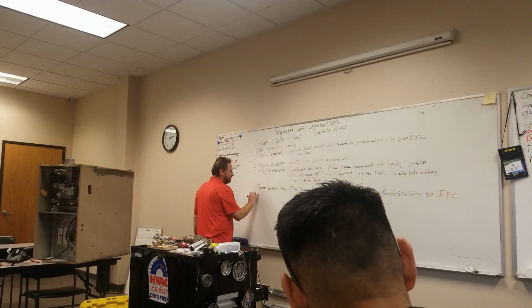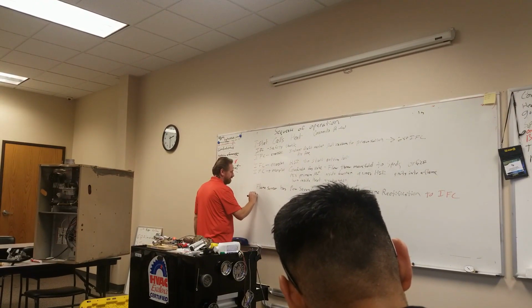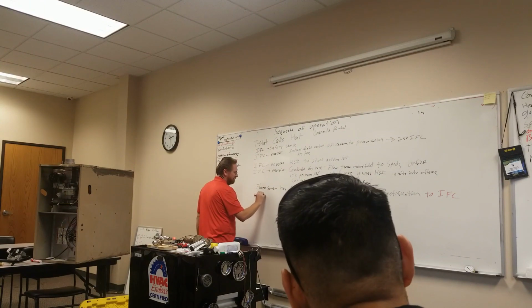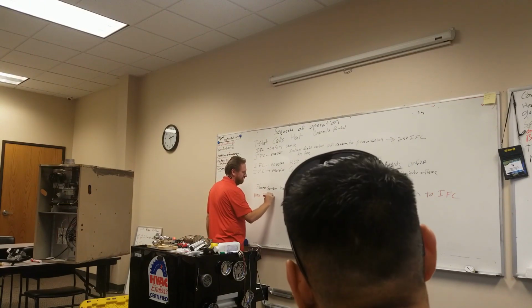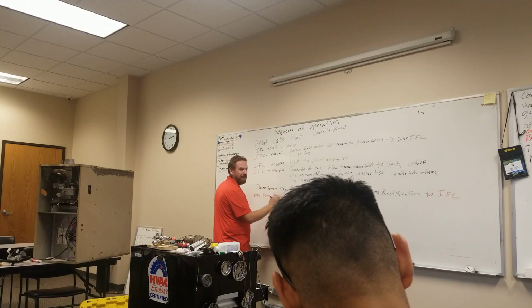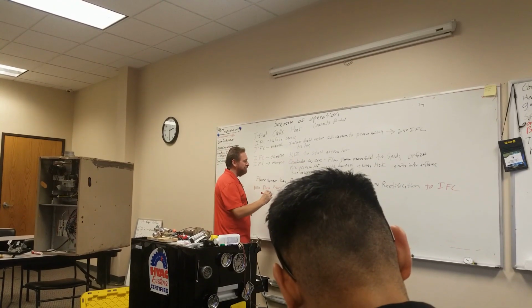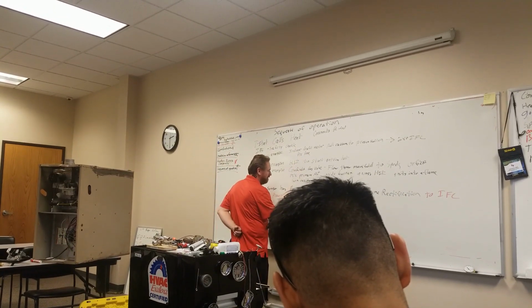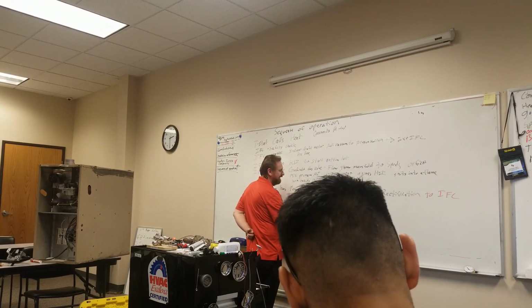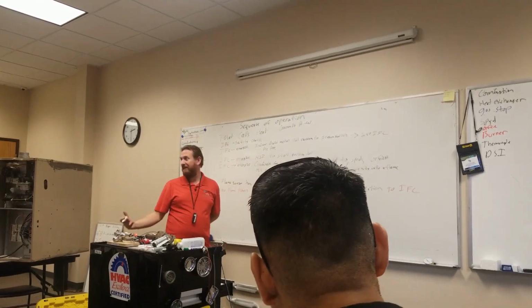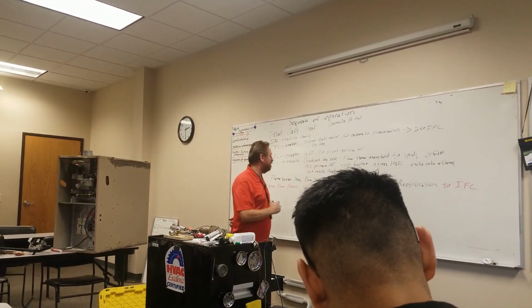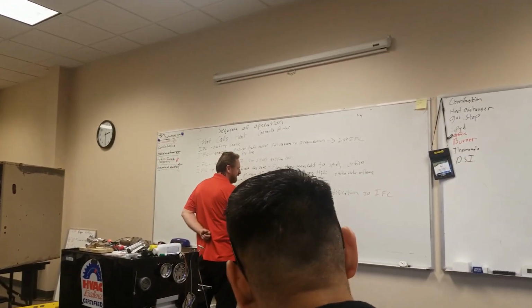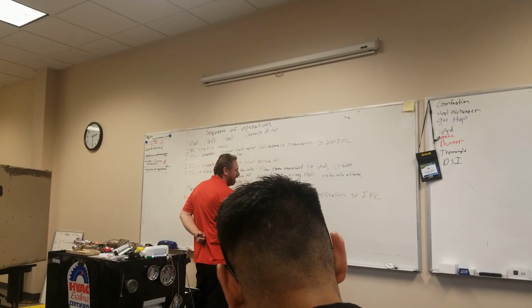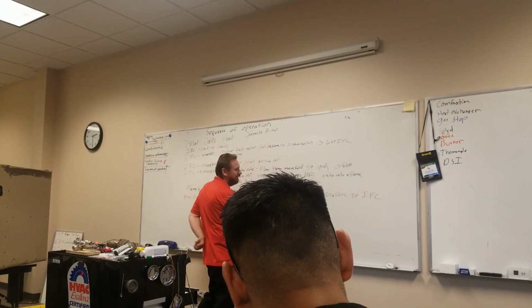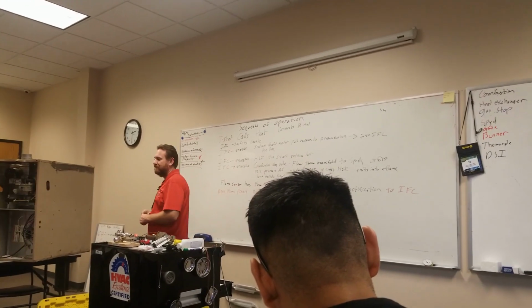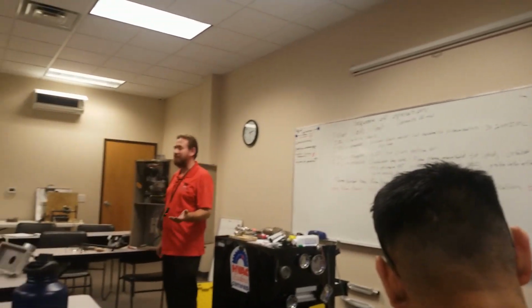Once the flame's proven, if we know that we have a flame, what we're going to do is shut off the hot surface igniter, right? Because we don't need it on all the time, do we? We've already lit the flames. We're going to shut off the hot surface igniter, and keep on the combination gas valve. Don't we want to keep the gas on? Keep the flames on? Yeah.